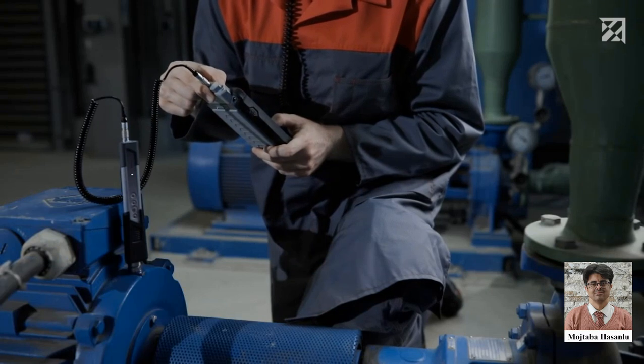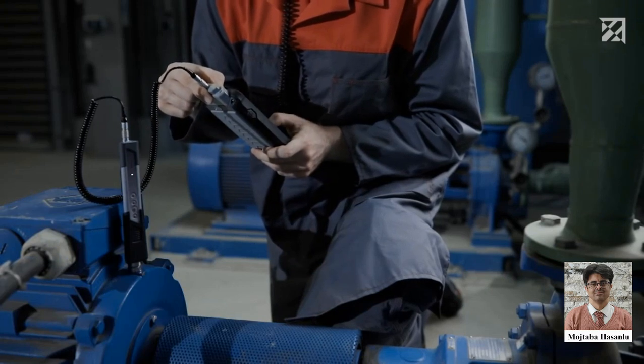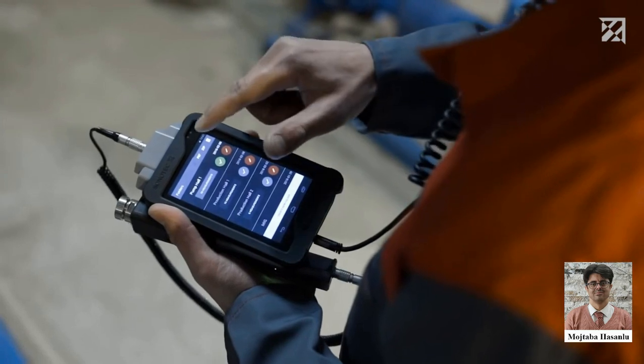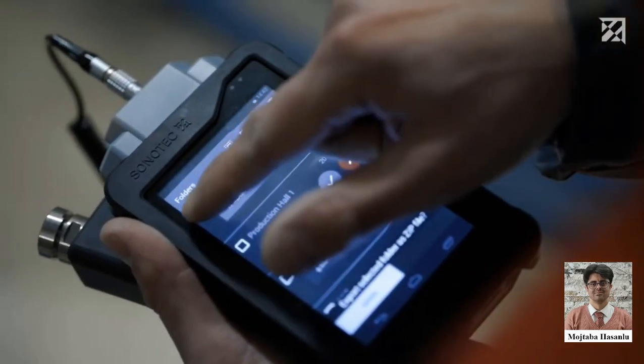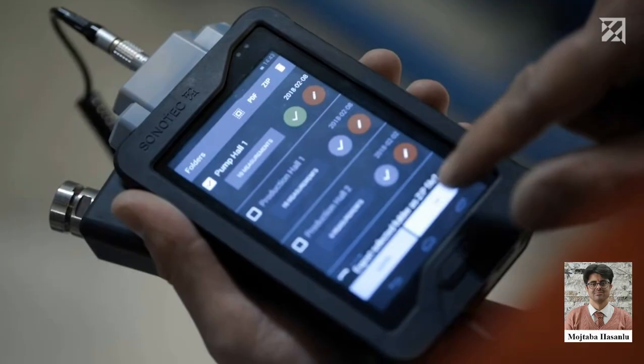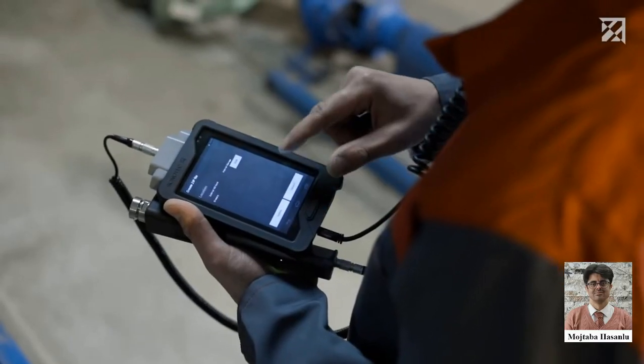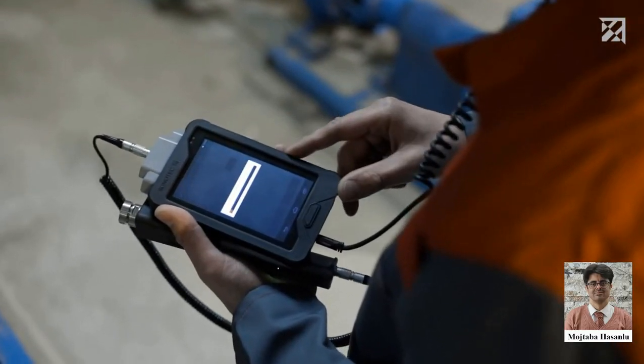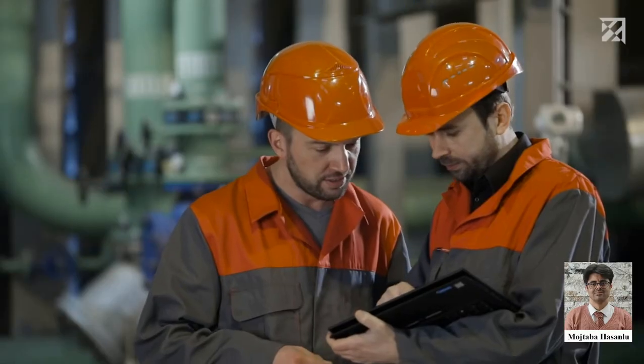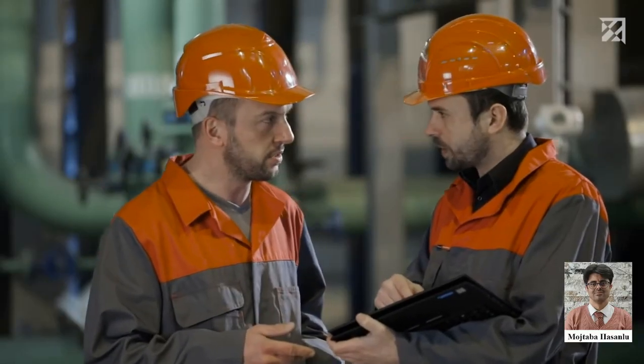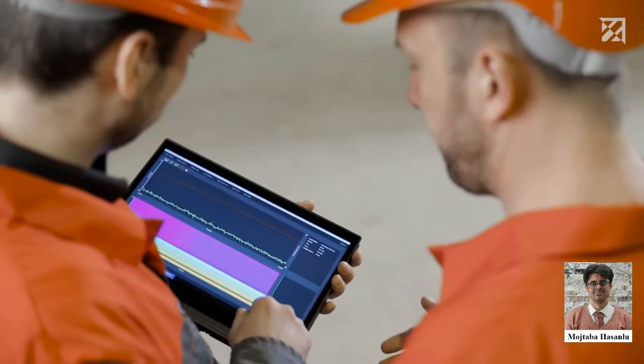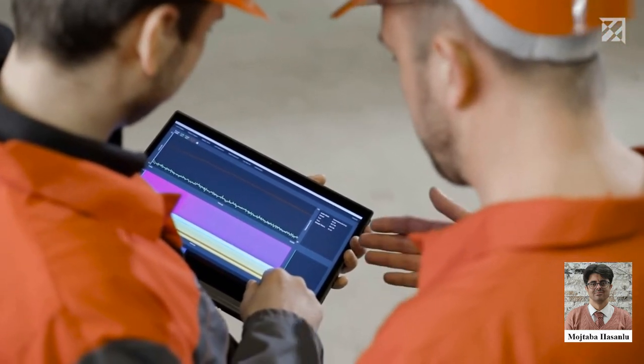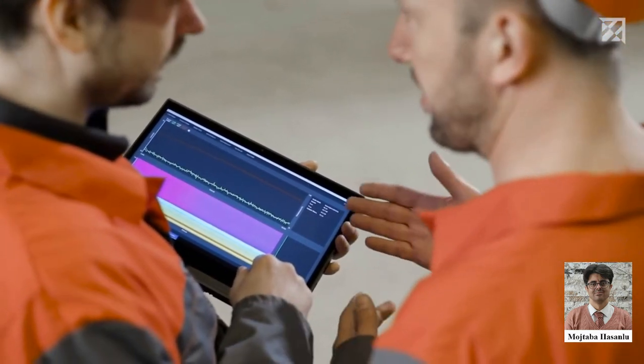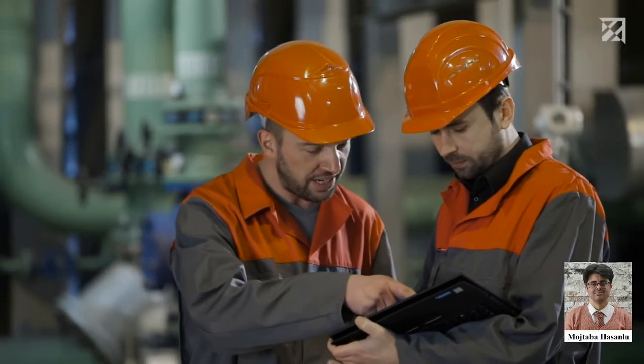The tester then adds photos, comments, and voice memos relating to the test point before moving on to the next one. Once testing is complete, the service engineer can create a report with just a few clicks. Alternatively, the data can be evaluated on the computer using the PC software. The Data Viewer software allows the user to play back all recorded testing data. Relevant areas can be investigated in more detail, and the data can be exported for further processing.